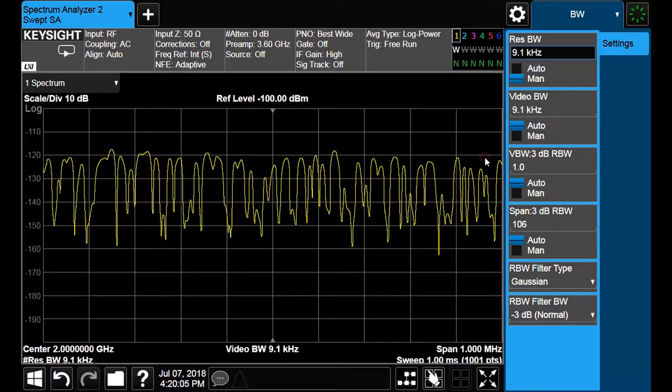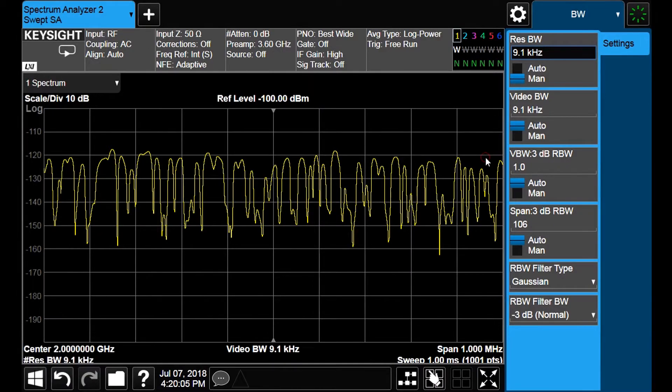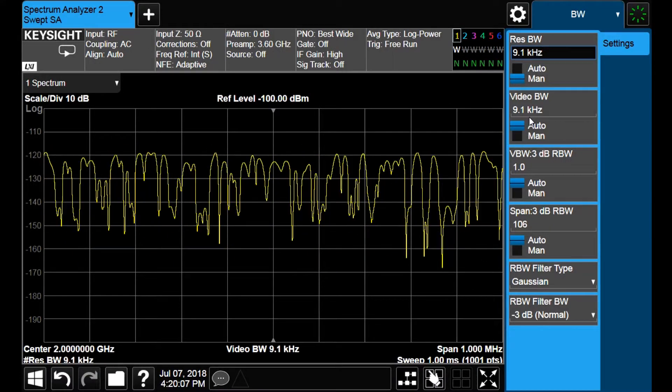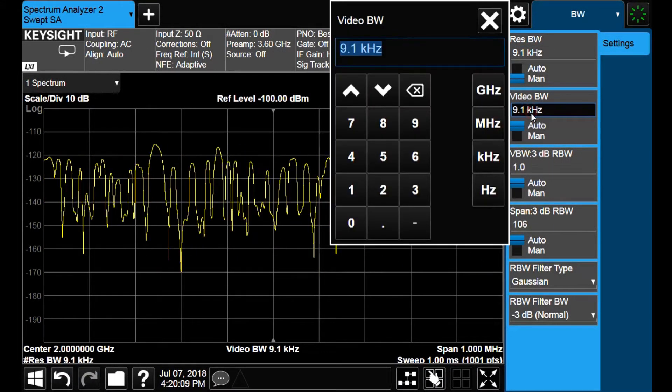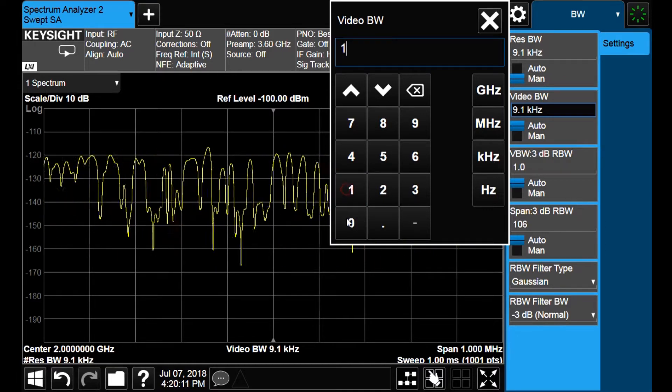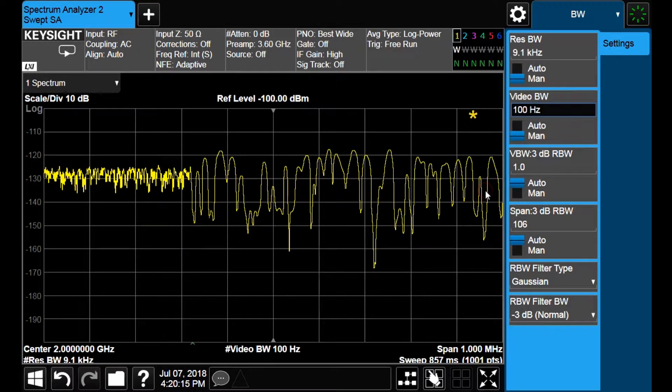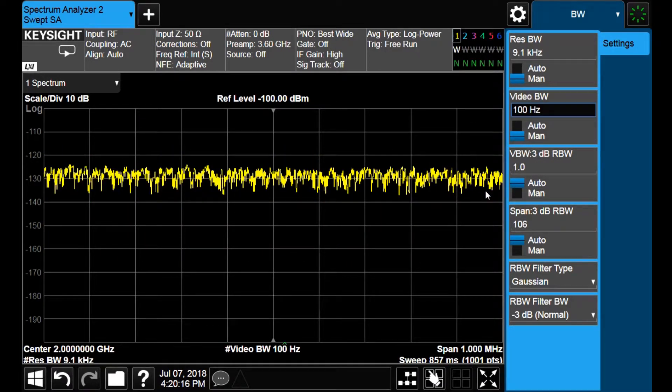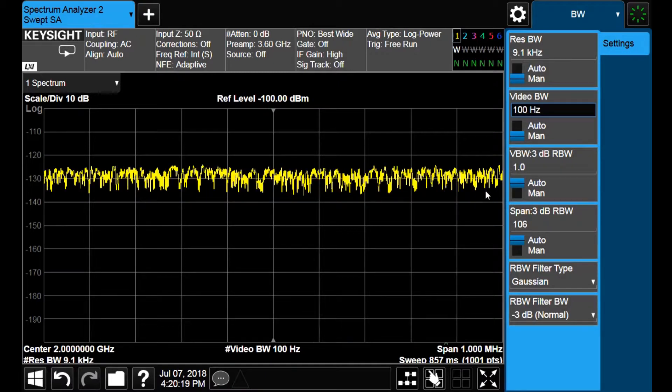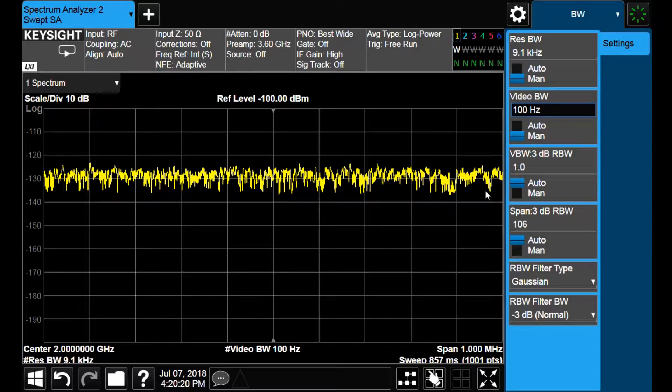Let us come back to the resolution bandwidth of 9.1 kHz and reduce the video bandwidth instead. Let us specify a video bandwidth of 100 Hz and we see that the sweep time has also increased significantly as compared to the original configuration. This time is more than 800 ms. Observe that now we have smoothed the trace, facilitating the detection of weak peaks above the noise, but the noise level itself is not changed.